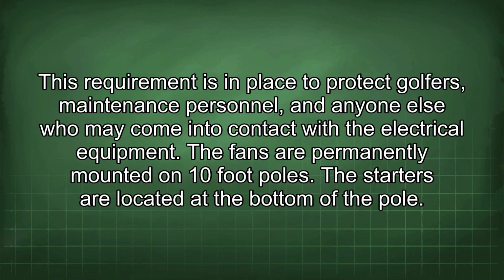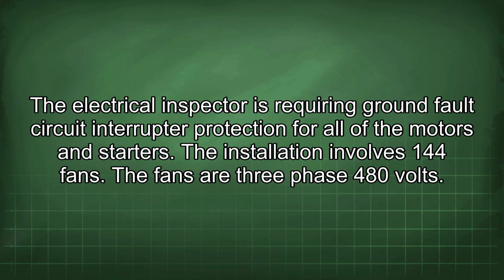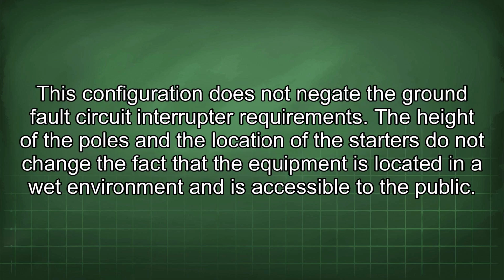This requirement is in place to protect golfers, maintenance personnel, and anyone else who may come into contact with the electrical equipment. The fans are permanently mounted on 10-foot poles. The starters are located at the bottom of the pole. The electrical inspector is requiring ground fault circuit interrupter protection for all of the motors and starters. The installation involves 144 fans. The fans are 3-phase 480 volts. This configuration does not negate the ground fault circuit interrupter requirements.